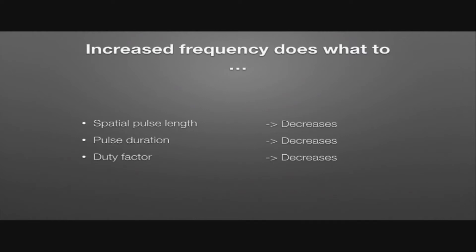With the spatial pulse length, increased frequency is going to decrease it. Because with increased frequency, we've got a shorter wavelength. If we've got three to five cycles per pulse, with a shorter wavelength, that means we're going to shorten the spatial pulse length. In terms of pulse duration, with increased frequency we reduce the period — the time for one wavelength — and again, if there are three to five cycles per pulse, the whole pulse duration will be decreased with increased frequency.